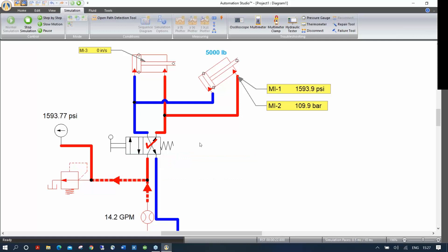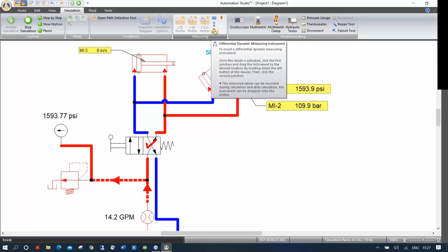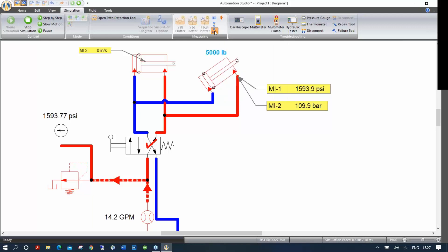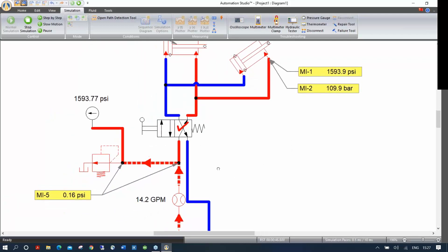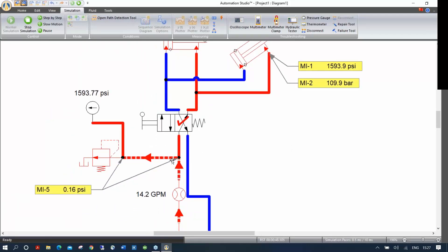You can also show differential pressure using the two-node differential tool. Click it, go to a node, click, drag to wherever you want, then place the second node. This displays the differential pressure between two points. Right now I see a difference of 0.16 PSI between these two points — meaning I'm losing 0.16 PSI in this hose.